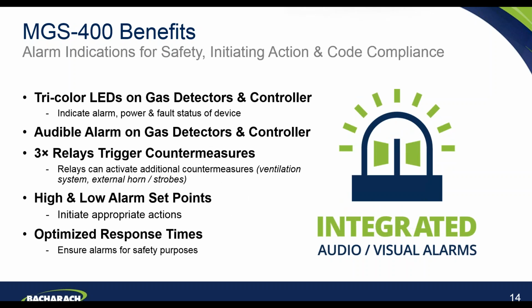As mentioned a couple of times already today, the key application for the MGS-400 series is to assist in compliance with the relevant standards and codes. In line with that, the product has been designed to feature a number of features that support in that. So, for example, it has tricolor LEDs on both the gas detectors themselves and also on the MGS-408 controller to indicate alarm, power, and fault status. It has inbuilt audible alarms, again on both the gas detectors and the controller.